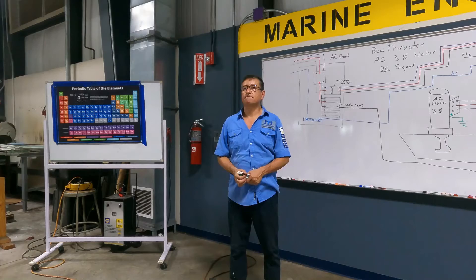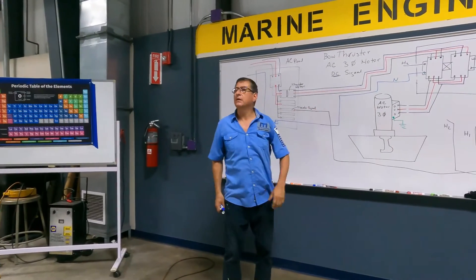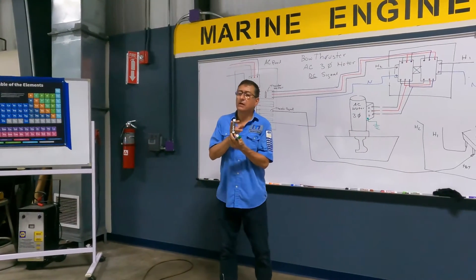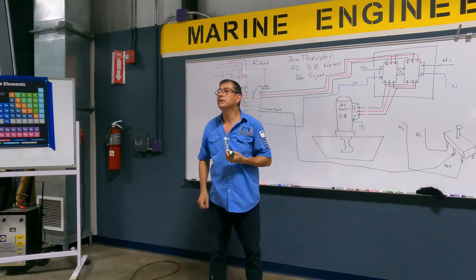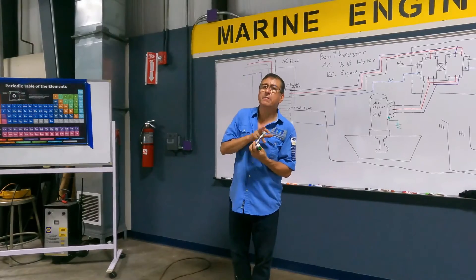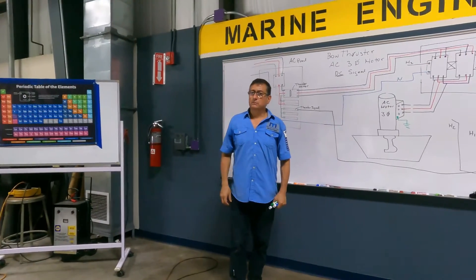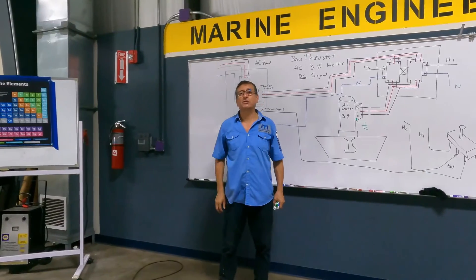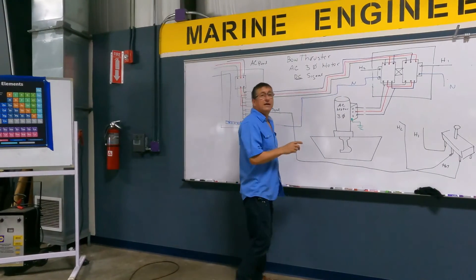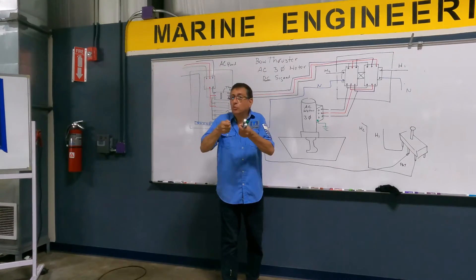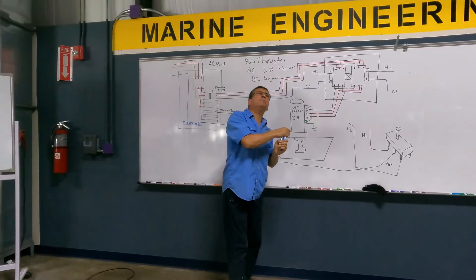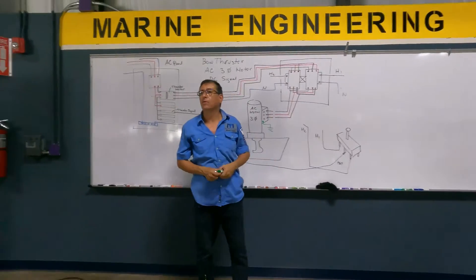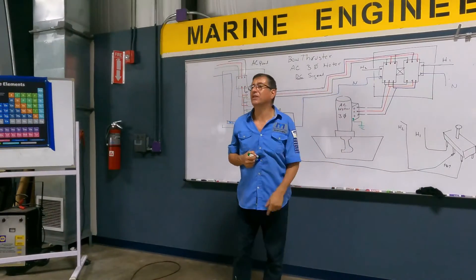Let us do a small troubleshoot on that motor. The captain complained that the bow thruster is moving to starboard side but not port side. You need to verify the contactors. Bring an external AC 120V signal and connect it here — the bow thruster moves in one direction. Bring the signal to the other contactor — nothing. The problem is that second contactor is finished.